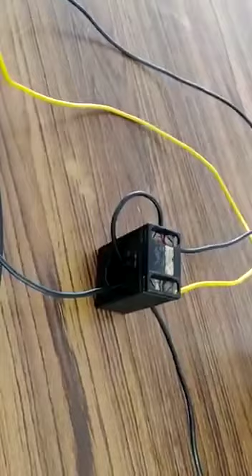Now I will load and I will show you different readings. So supply is on. Now load is being given in this circuit. This is my secondary of CT reading, 0.1 amps. 0.1 into 10, 1 amps. This is the current actually flowing in the load. So whether that 1 amps is correct or not can be verified through this meter.